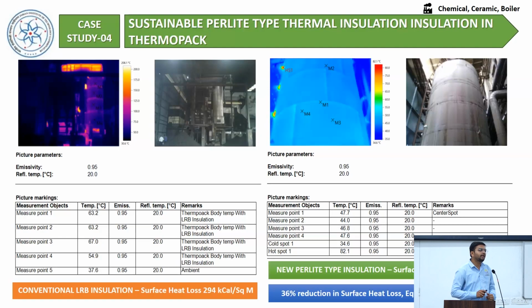This insulation also has more than 50 years of life, as it comes in a solid section manner. So the insulation can be damaged only if there is mechanical damage. This is a good insulation replacement done by the industries, and they have almost 36% reduction in the surface heat loss, which accumulates to a 7% reduction in the fuel consumption.